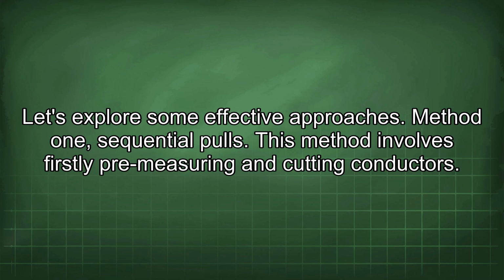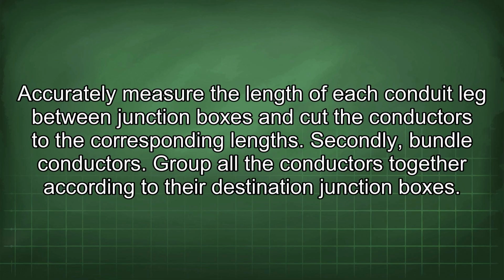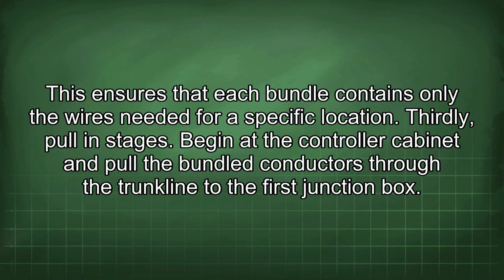Method 1. Sequential pulls. This method involves firstly pre-measuring and cutting conductors. Accurately measure the length of each conduit leg between junction boxes and cut the conductors to the corresponding length. Secondly, bundle conductors. Group all the conductors together according to their destination junction boxes. This ensures that each bundle contains only the wires needed for a specific location.